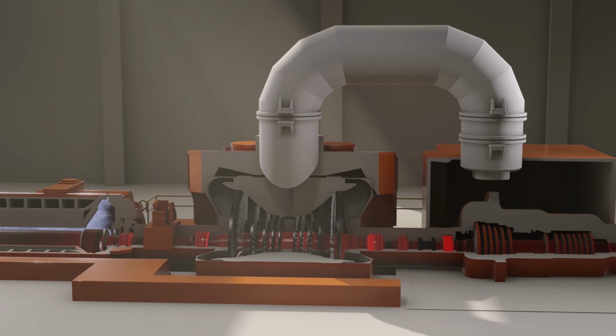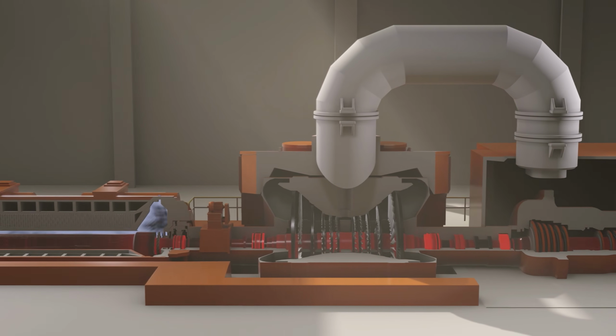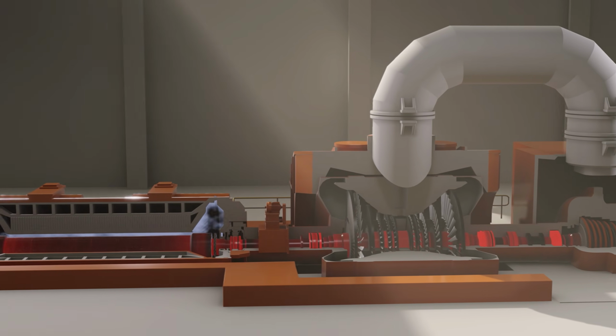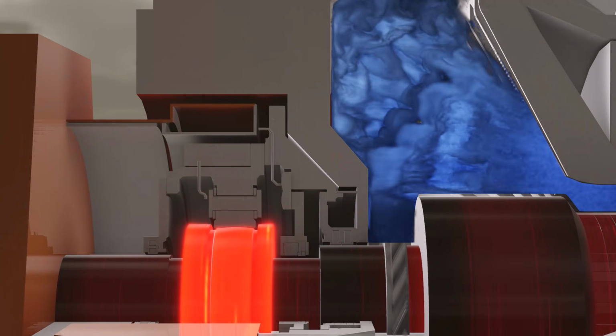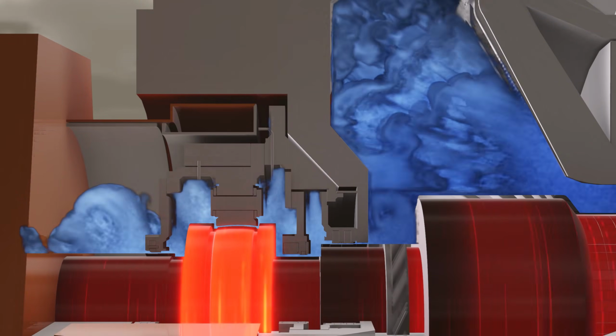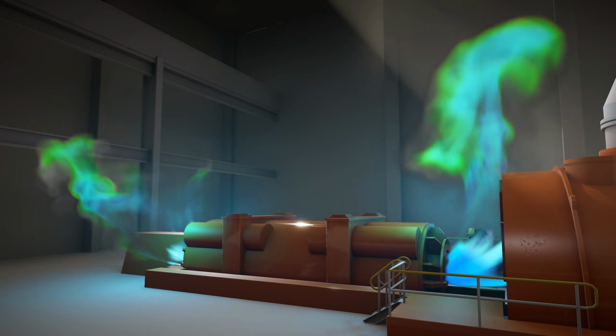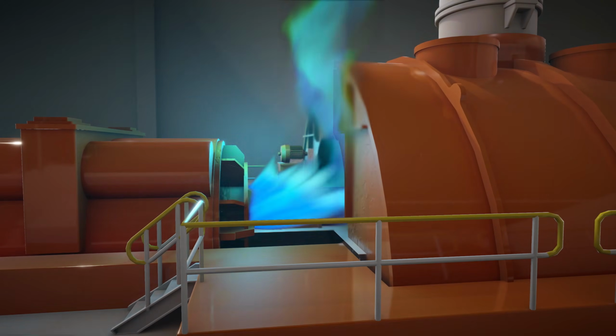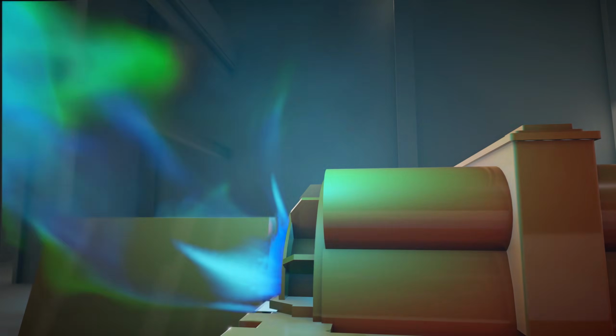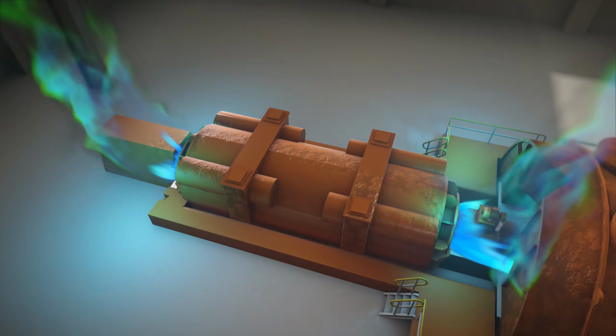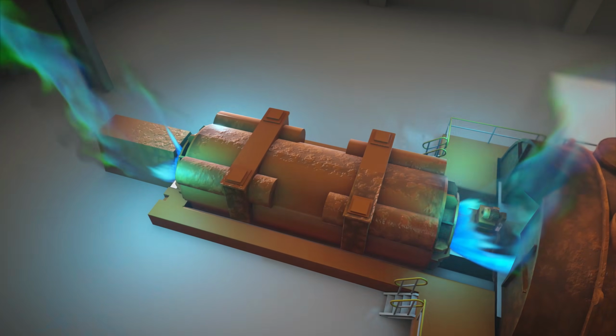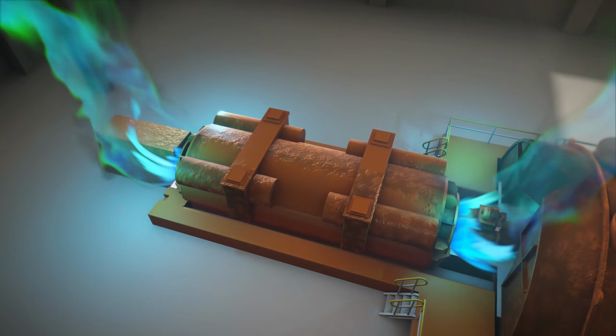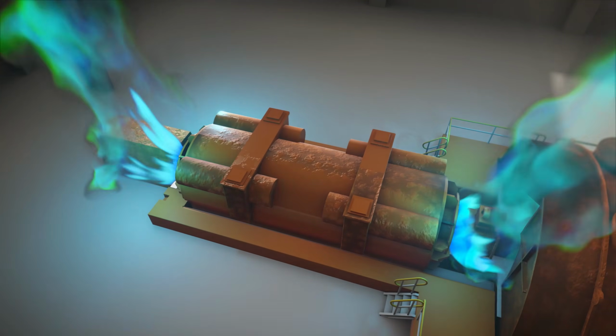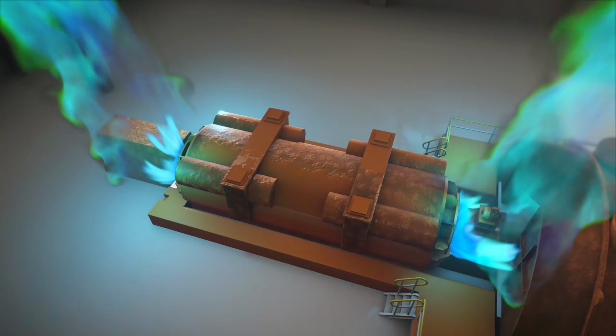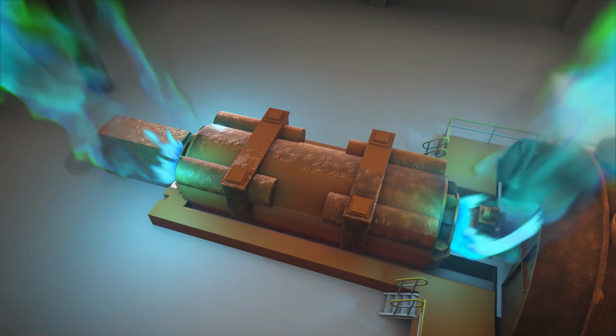Without all these pumps, the oil pressures in the bearings drop and the shaft begins grinding metal on metal and producing heat. And without seal oil pressure, hydrogen gas begins escaping from the generator and combusting in the air. On top of this, the loss of AC power means that none of the cooling systems critical for the safe operation of the turbine generator and generator transformer are available. These begin to heat up.